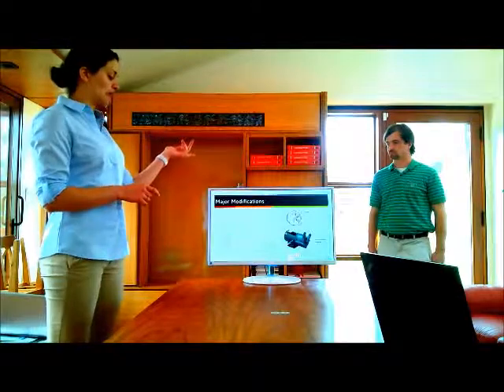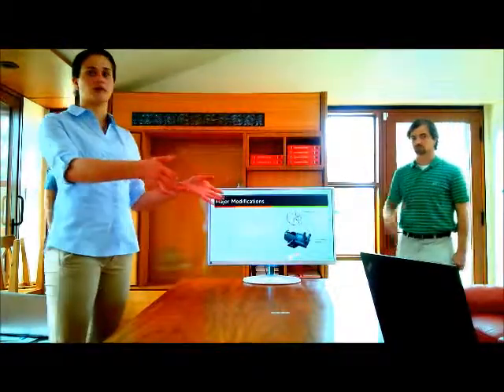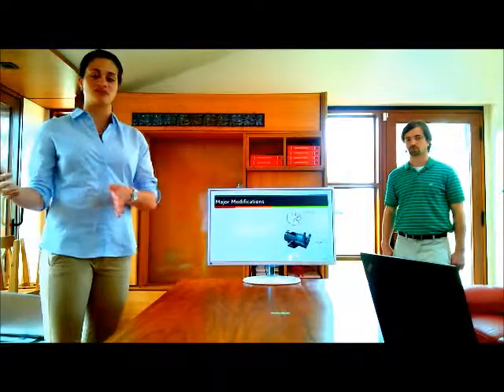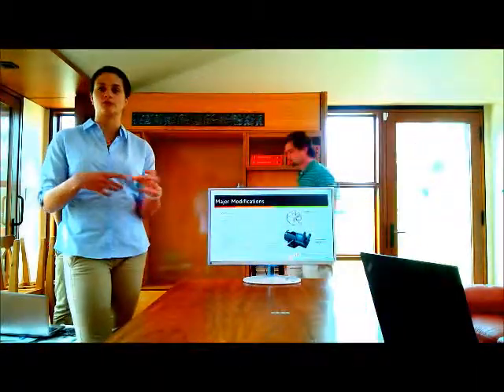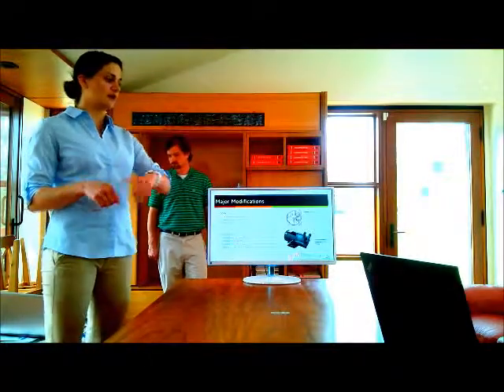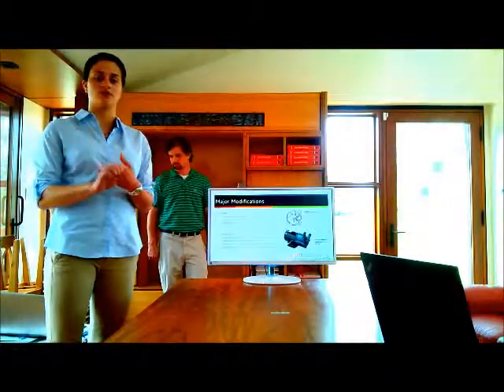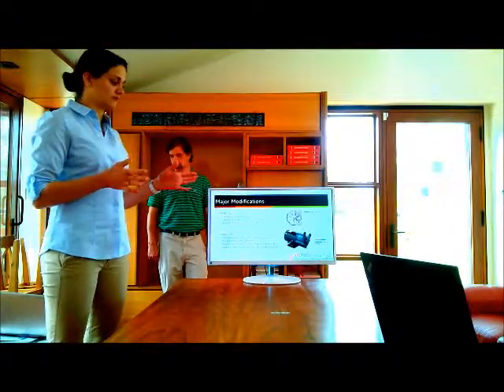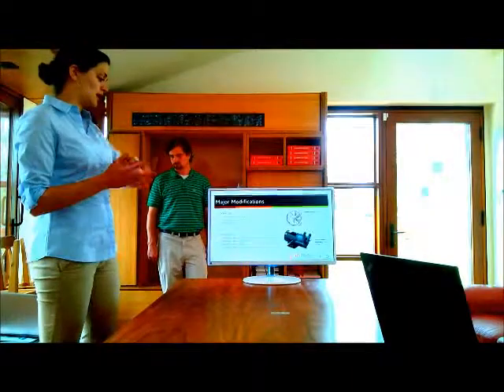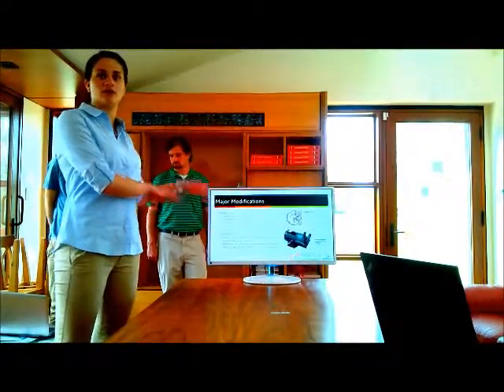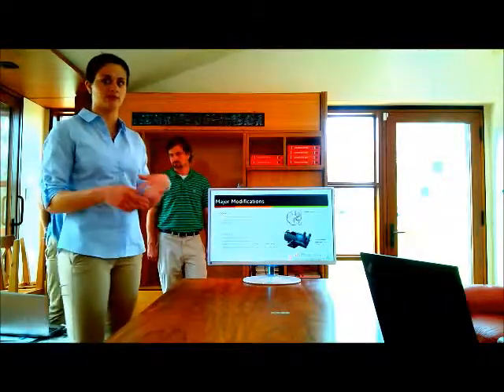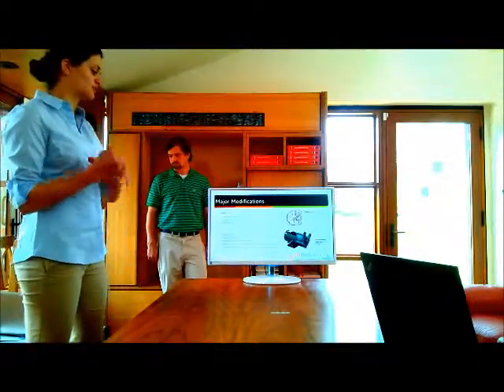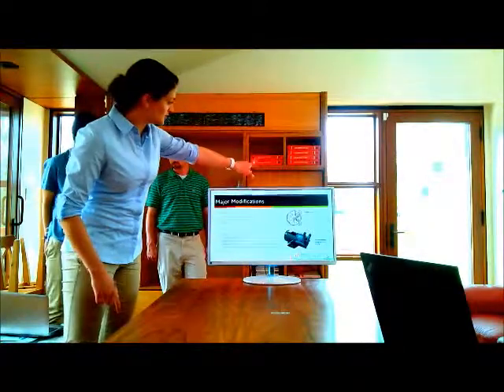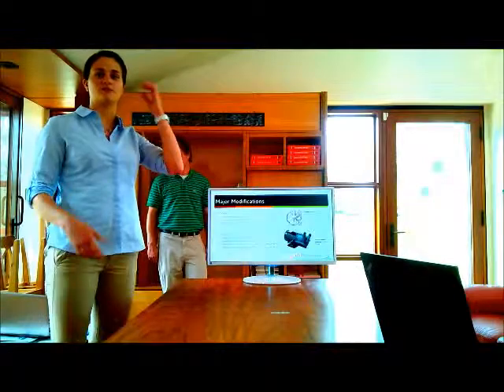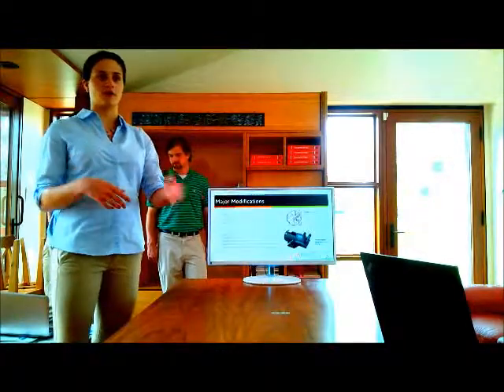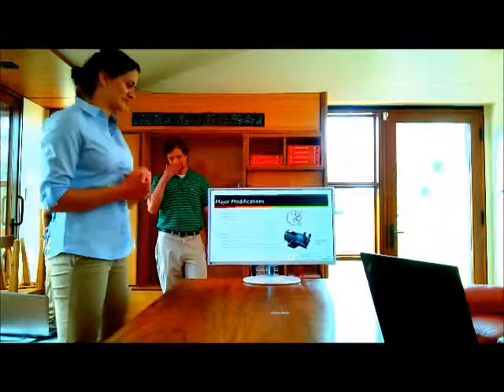And so for the outdoor unit, the container holding all of the solution was shifted. So a lot of the PVC pipes and connections were broken and cracked. So we had to replace a lot of the PVC pipes, a lot of the connections, and 2 of the pumps and a fan, since a lot of that system was shifted. And then Song helped us add a cover to the back of the container so that debris wouldn't flow in and mix in with the solution when it was running. And then we restored water pressure to the tubes, the white tubes that come up into the evaporation tubes, because we actually found a tube that was just leaking water into nowhere, and so the pipes weren't working.